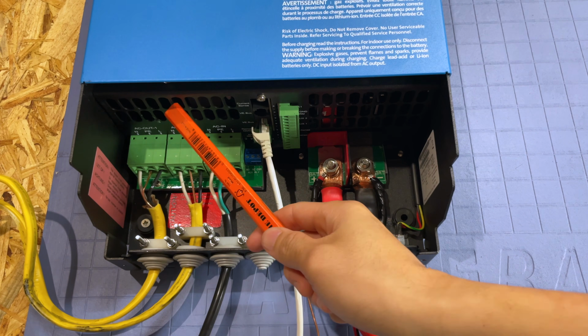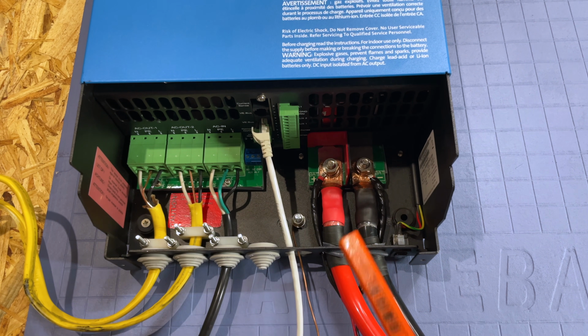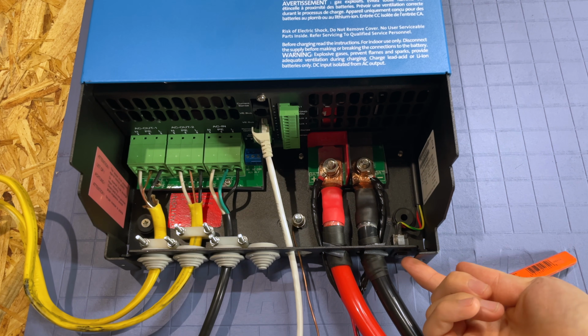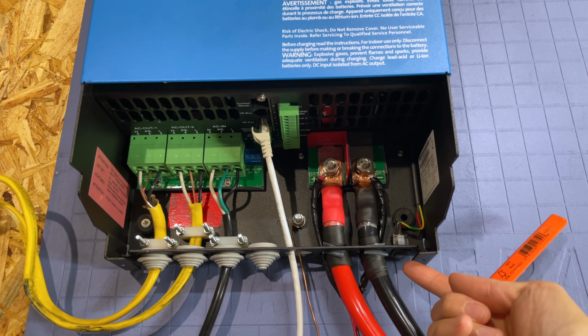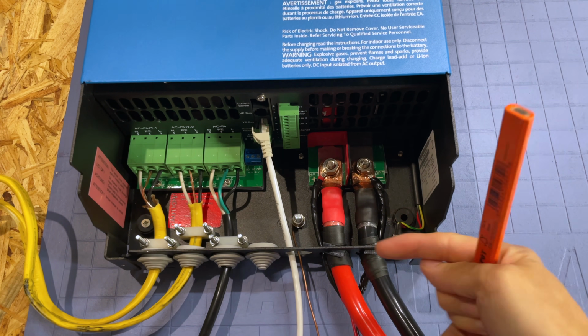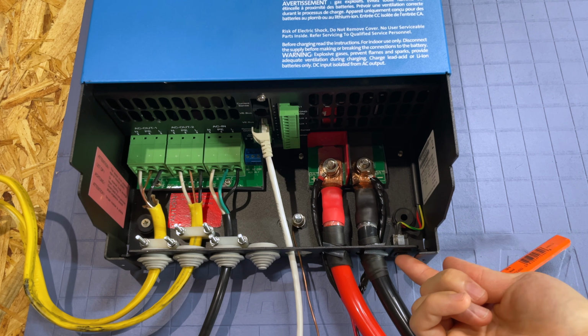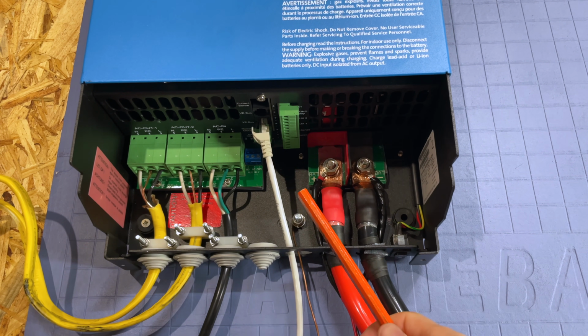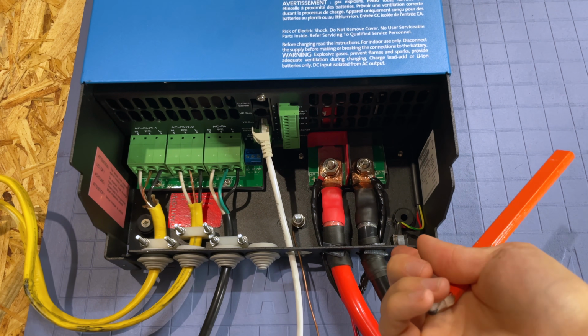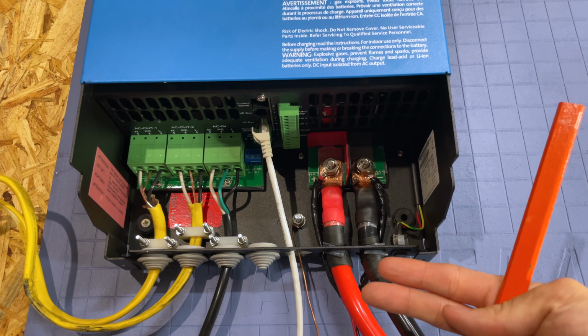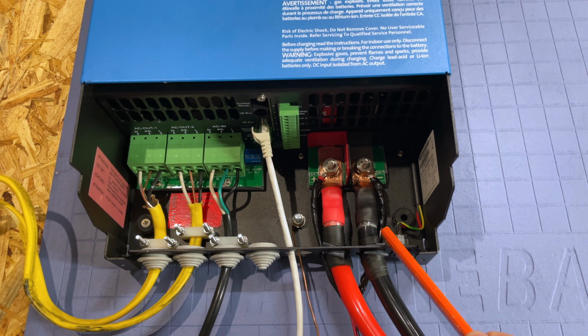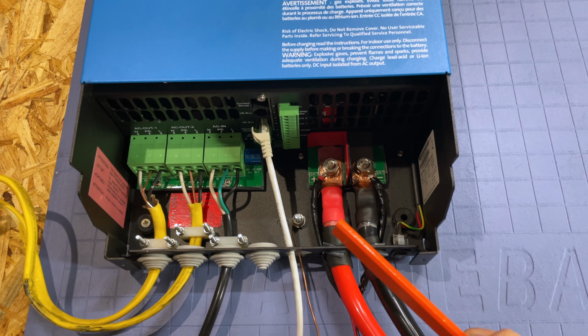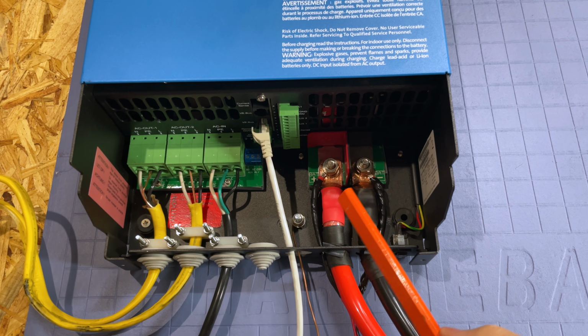There's a bunch of ventilation holes here, on this side and this side. The switch for turning the inverter on is here. If you pull it towards you, option 1 or one line, it's on full mode, inverter mode, charger mode, whatever. If you flip it towards the back, 2 stripes or 2 lines, you're operating in charger mode only, so the inverter function won't work.